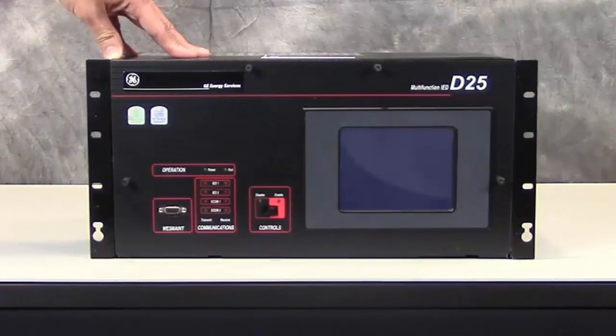It has integrated transformer monitoring logic, which allows it to work in a transformer monitoring capacity. Also included, though not as popular, is definite time protection and breaker failure protection, included in generation 4 of the D25.